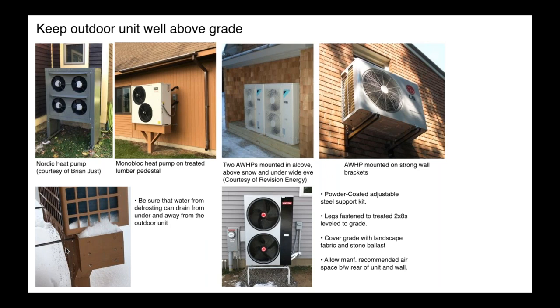And the more the bathtub grows, the less condensate is going to drain, and you can damage the coil. The ice can cause damage. And actually, I know of one case where it was a ductless mini split, but it's the same argument. They actually split the refrigeration piping due to ice buildup at the bottom. So get the unit up. There are some kits available on the market today. This gets the unit up about 14, 15 inches. We put some landscape fabric and some crushed stone down just so we didn't have grass growing up under the unit. So get it up above grade.